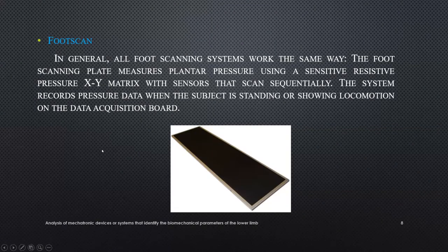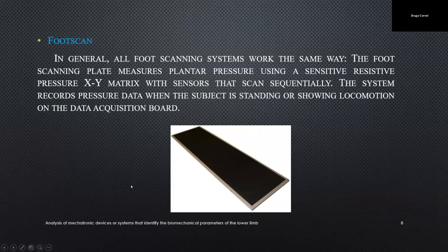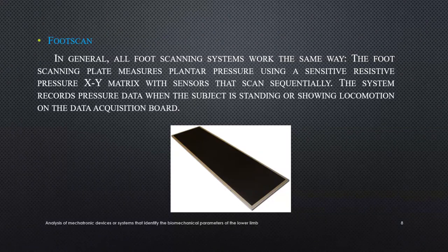Generally, it works measuring plantar pressure and uses a sensitive resistive matrix with sensors that scan sequentially. The system records pressure data while the subject is standing or moving on the plate.